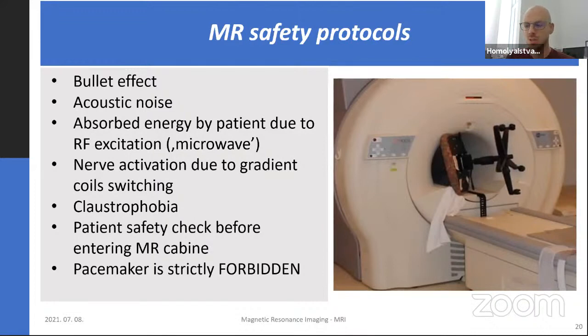Other patient comfort features: there can be acoustic noise during the measurement, but headsets are very useful. And we need to pay attention to the energy absorbed by the patient due to the radio frequency excitation. We know that the main goal is not to heat the patient, but as a side effect, sometimes it can happen, but it's always monitored, and there are safety protocols which prevent overheating. And also, as we are turning these gradient currents on and off, we can induce nerve activation very easily.